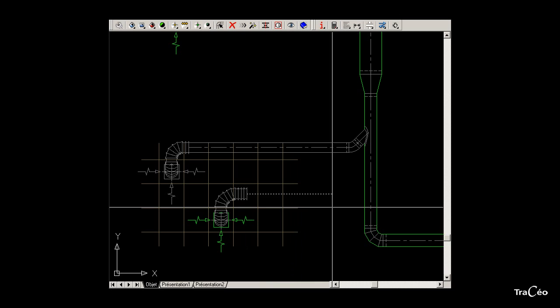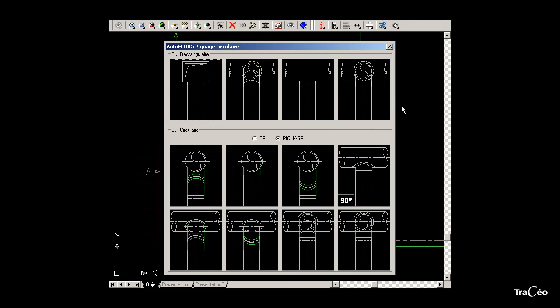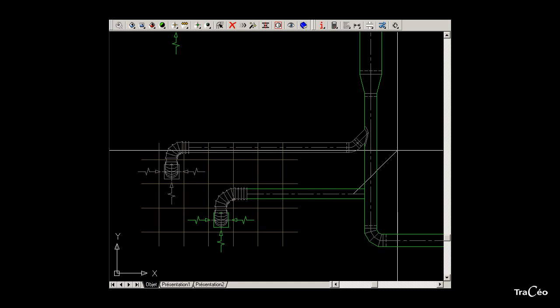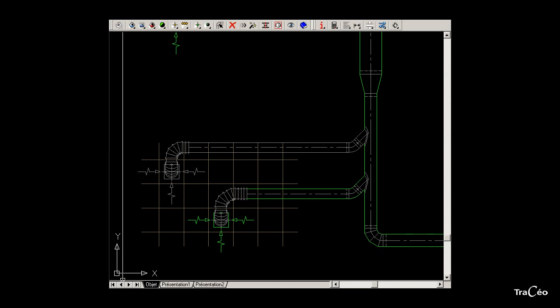Right-click and select switch to rigid and draw a rigid conduit. Right-click to call the connection option and choose the circular duct to circular duct connection, but specify 45 degrees instead of 90 degrees. Then select the duct to connect to and click to indicate the direction. The command draws the connection and the elbow, and the operation is complete.